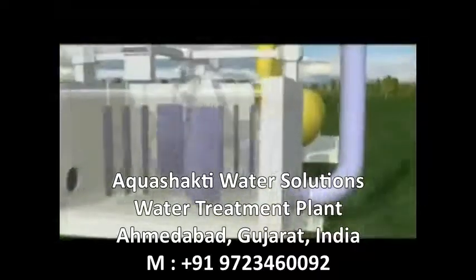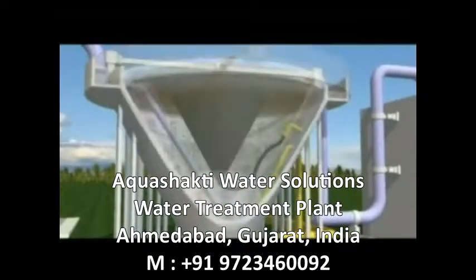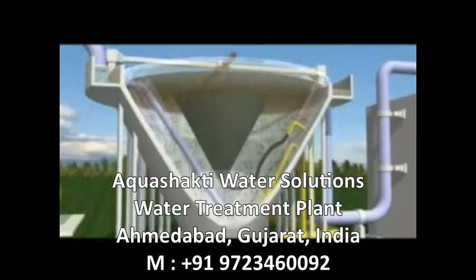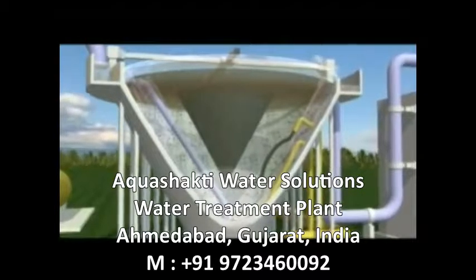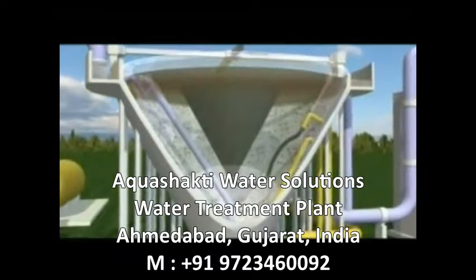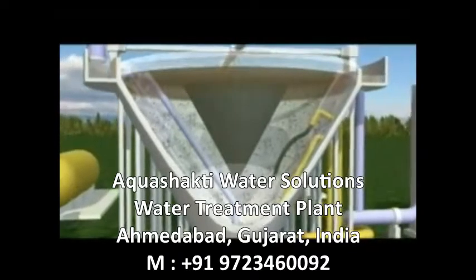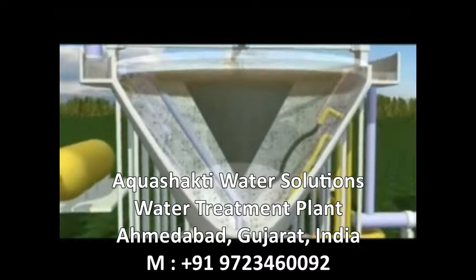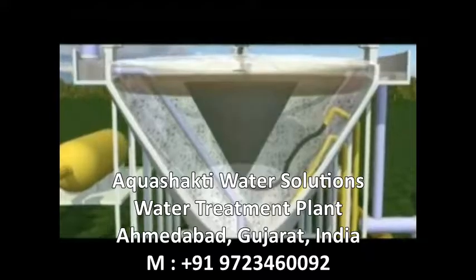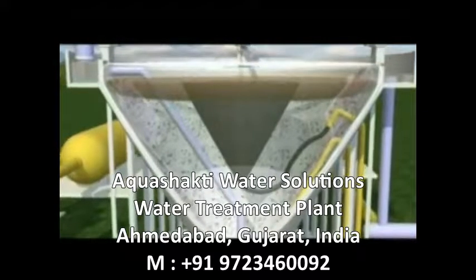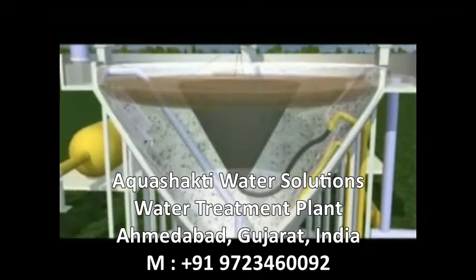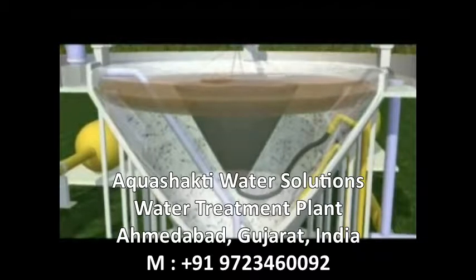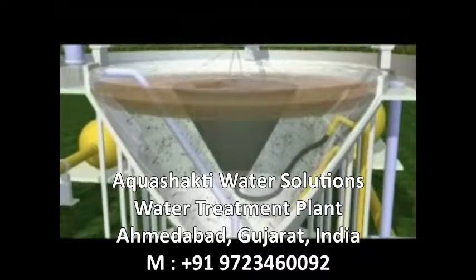Next comes the clarification process. The flock forms itself into sludge and is separated in a specially designed tank called a clarifier. This sludge layer is called the sludge blanket. To control the blanket, sludge is periodically drained off, concentrated and removed for safe disposal. Particles filtered out on the RGF, the rapid gravity filter, are removed by backwashing.